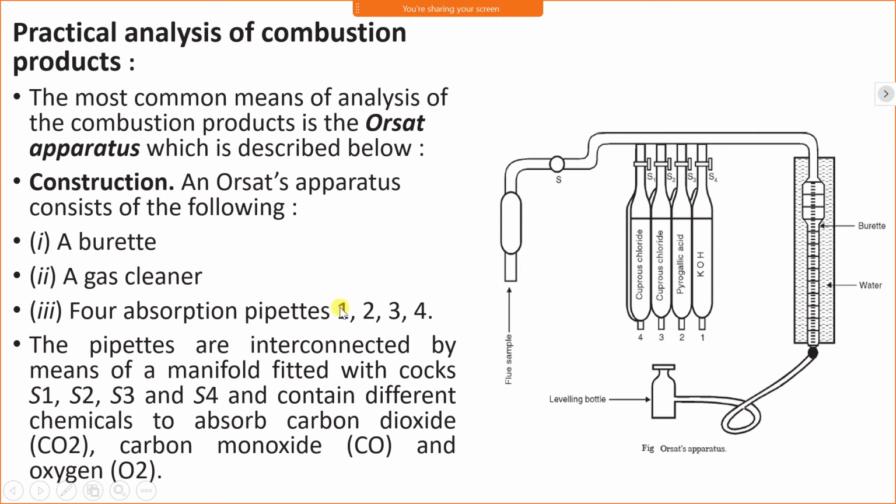S4 is for first, S3 is for second, S2 is for third, and S1 is for fourth. The sequence of cock and pipette is different and they contain different chemicals to absorb carbon dioxide, carbon monoxide, and oxygen.